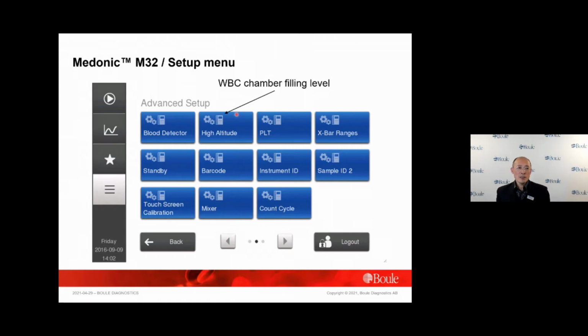High altitude actually changes the WBC chamber filling level. Even though the instrument can tolerate quite a big variation of altitude, the user can use this setting to solve some problems with HGB measurement. Some HGB flags are related to the WBC chamber filling levels, and this can be used as a troubleshooting tool to check if the HGB problem is due to the filling level.